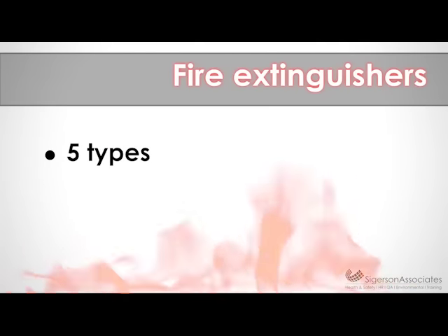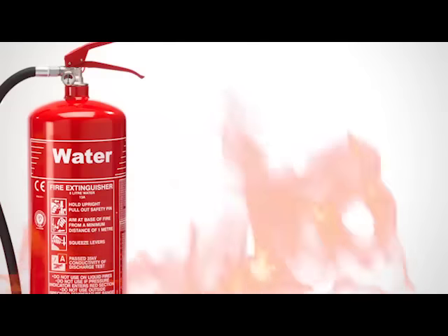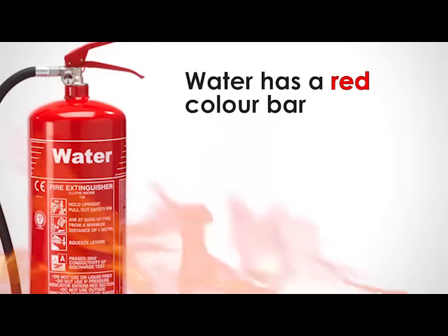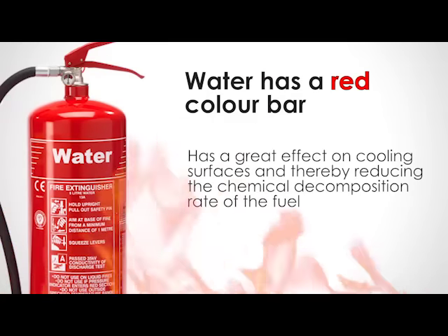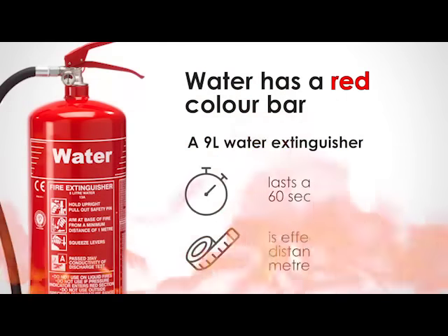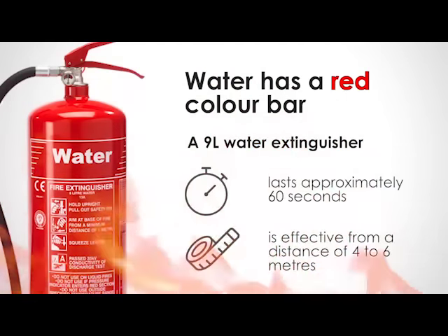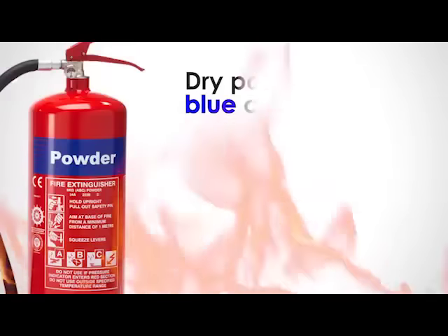There are 5 main types of fire extinguisher. A colour bar at the top of the fire extinguisher will denote its type. These are water. Water has a red colour bar. Water has a great effect on cooling surfaces and thereby reducing the chemical decomposition rate of the fuel. A 9-litre total discharge water extinguisher will last for approximately 60 seconds and is effective from a distance of 4 to 6 metres.